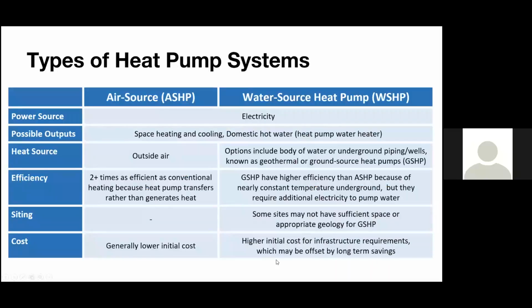Looking at the types of heat pumps here, I'm going to compare air source heat pumps to water source heat pumps. I'm sure most of you might have heard of both of these, air source and water source. It refers to where this machine is rejecting or injecting its heat. Where is it getting its heat from in the winter, and where is it releasing its heat in the summer? An air source heat pump is usually an outdoor machine. The condenser unit that's outside, that's of course air source. A water source heat pump is a machine that's very, very similar, but it's going to get its heat from or dump its heat into a water loop. We normally call it a condenser water loop, which comes up as you need somewhere to put the heat or extract the heat from.